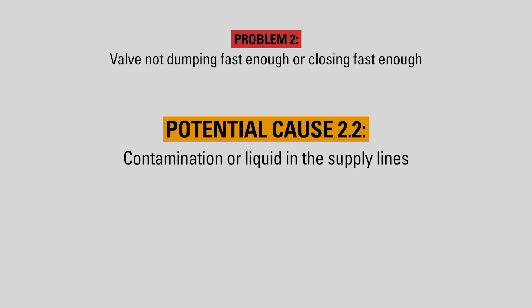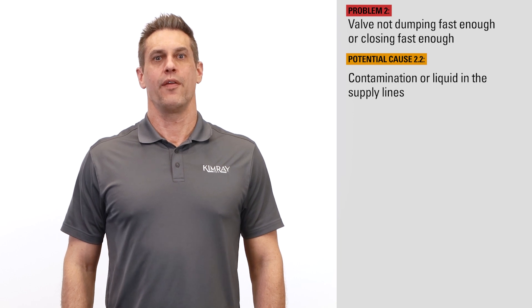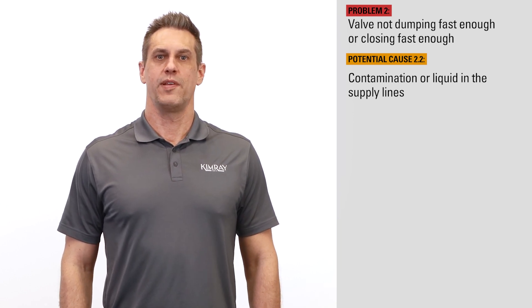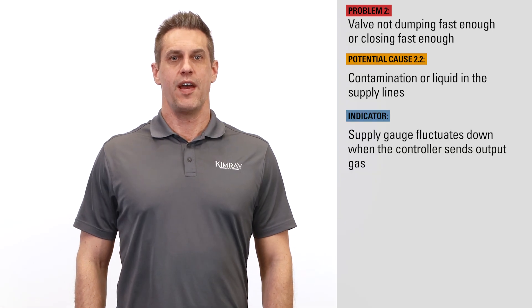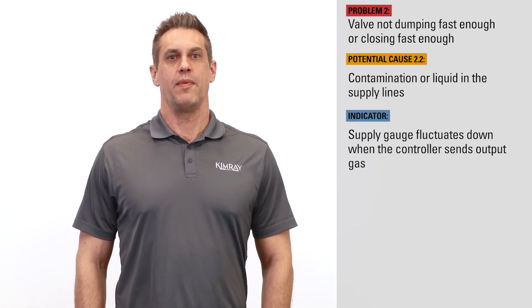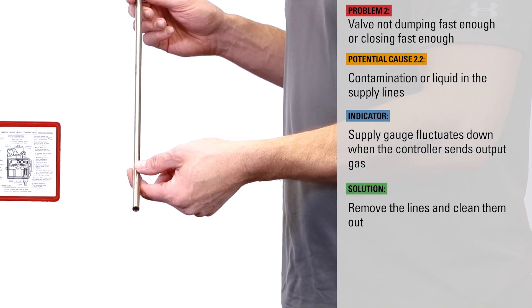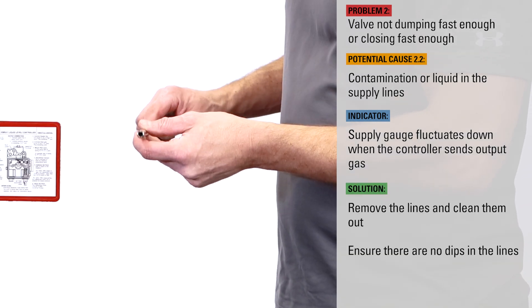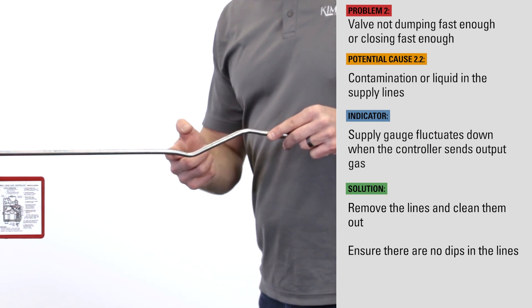If the supply lines coming into the controller are impeded by liquid or other contaminants, the flow of supply gas could be slowed down. If the supply gauge fluctuates down when the controller sends output gas, this may be an indication that the supply lines are restricted. Remove the lines and clean them out. Ensure there are no dips in the lines where moisture could collect and pool.